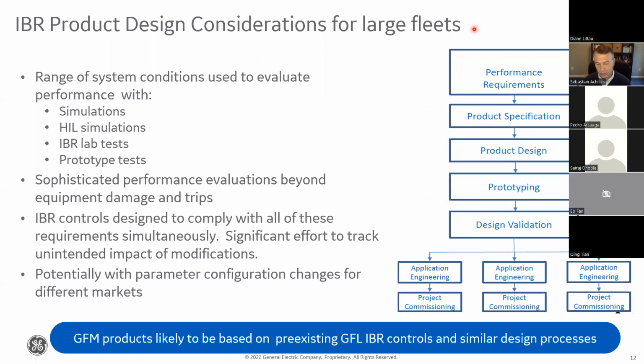For example, you could find that a particular place requires the active power to recover very quickly after a fault—a particular country or grid code may require that. At the same time, if you have a short circuit ratio that is extremely weak, like Pedro was describing, say 1.3, you may not be able to recover power so quickly, because otherwise the system collapses.